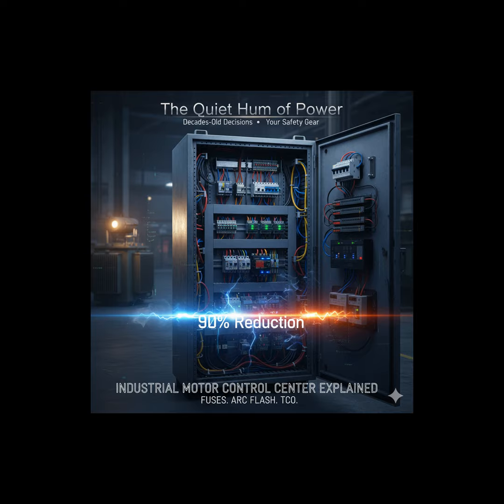Right. At the heart of it, you have the contactor. That's the remote switch that turns the motor on and off, getting signals from a PLC or some control circuit. But the true protector, the real bodyguard for the motor windings themselves, is the second component, the overload relay. And the distinction here is key, right? We're not talking about a massive short circuit yet. The overload relay is handling situations where the motor just draws too much current over time, typically because it's struggling. Precisely. If that conveyor belt gets jammed or a pump starts seizing up, the motor works harder, it pulls excess amps, and it heats up. And that heat is what kills the insulation. The overload relay detects that sustained excessive current before the motor is permanently damaged.